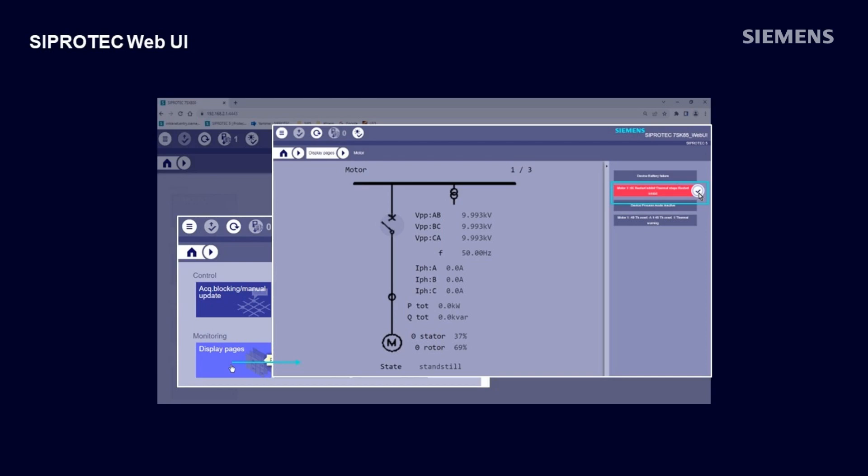On the right-hand side, we see acknowledgeable signals which were selected earlier in the DIGSI 5 information routing matrix. In our example, the temperature of the rotor is so high that another restart is not yet possible, which is indicated by the red color on the right-hand side. When this status changes, the color becomes green. The green color changes to the basic color when the signal is acknowledged.